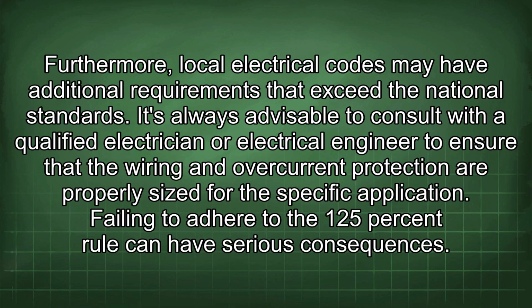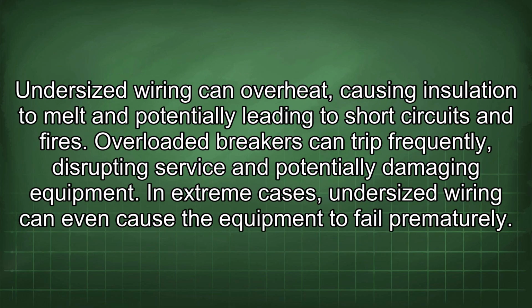Furthermore, local electrical codes may have additional requirements that exceed the national standards. It's always advisable to consult with a qualified electrician or electrical engineer to ensure that the wiring and overcurrent protection are properly sized for the specific application. Failing to adhere to the 125% rule can have serious consequences. Undersized wiring can overheat, causing insulation to melt and potentially leading to short circuits and fires. Overloaded breakers can trip frequently, disrupting service and potentially damaging equipment. In extreme cases, undersized wiring can even cause the equipment to fail prematurely.